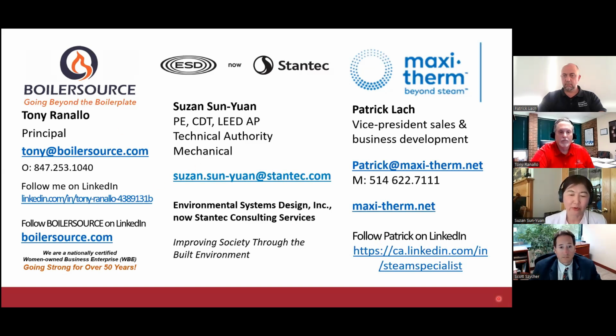And also, if you're using CHP and you generate your power on site, that waste heat is unavoidable, either as hot water or probably available as low pressure waste steam. That would be a terrific source to utilize for the cooling generation. So usually those are the two I've been seeing and would recommend.